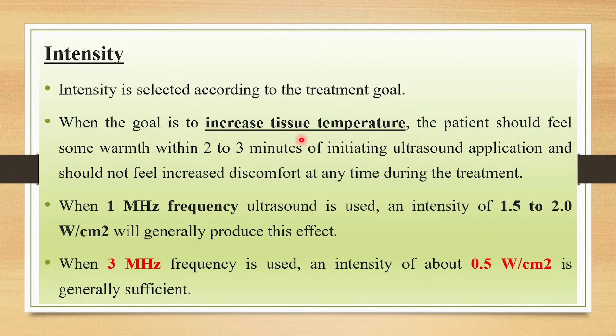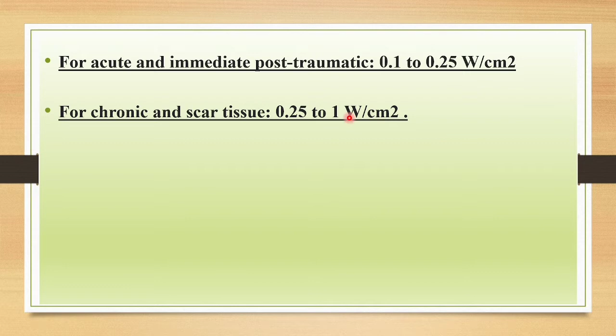When 1 megahertz frequency ultrasound is used, an intensity of 1.5 to 2 watts per centimeter squared will generally produce these effects. If our goal is to increase the tissue temperature and you are using 1 megahertz, that is a deeper penetration frequency, the intensity should be 1.5 to 2 watts per centimeter squared. If you're using 3 megahertz, that is for superficial conditions, an intensity of 0.5 watts per centimeter squared is enough to produce increased tissue temperature. For acute and immediate post-traumatic cases, we will use 0.1 to 0.25 watts per centimeter squared, and for chronic and scar tissues, 0.25 to 1 watts per centimeter squared.